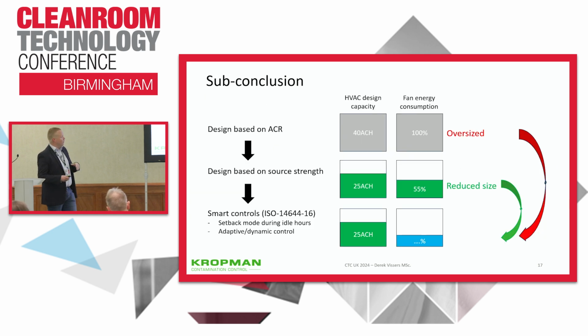And this brings me to the sub-conclusion on this part. So we have seen in the Netherlands already a lot of oversized systems which were initially designed based on air change rate. When you design based on the source strength, you have a reduction on energy consumption, but also a reduced size HVAC system, meaning the footprint of your facility is reduced. So you need less space in your technical areas. And of course, energy consumption can be improved more by smart controls.